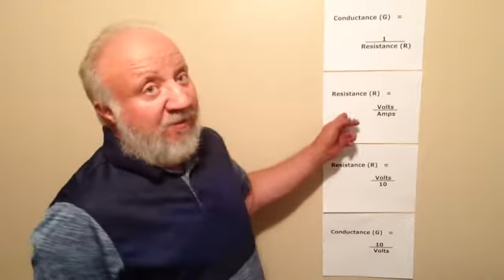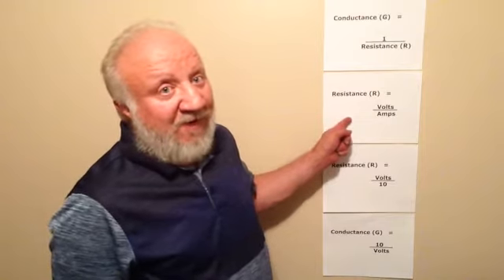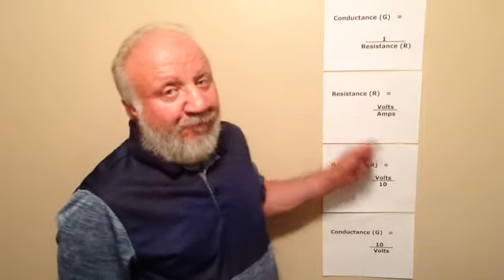If we make all our measurements using the exact same current value, then all we really need is the voltage drop. This is because of Ohm's law, where resistance equals volts divided by amps. If, for example, we use a power supply that provides 10 amps of regulated current, then the resistance would be 1/10 of our voltage drop reading.